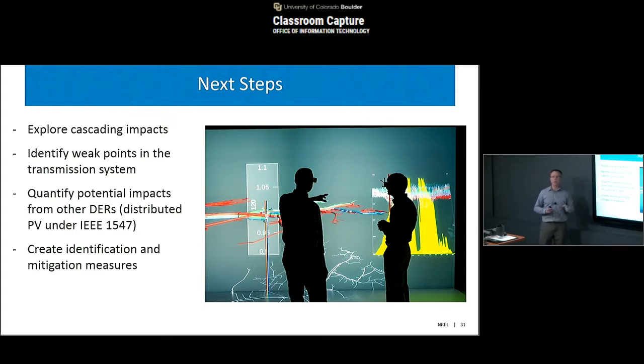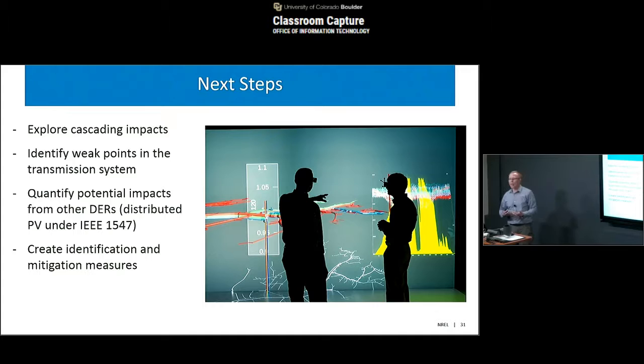One thing we need to do is explore cascading events: if you start to have voltage or frequency issues, something trips off, then something else trips off, then something else trips off, and that's how you cause blackouts like the 2003 Northeast blackout. By doing this, you can identify weak points in the transmission system and understand where we need to reinforce it against these types of contingencies.